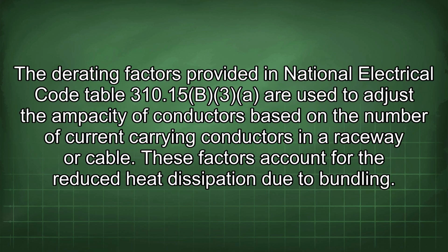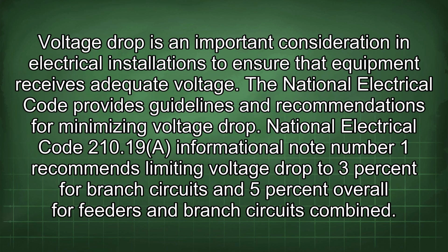The derating factors provided in National Electrical Code Table 310.15(B)(3) are used to adjust the ampacity of conductors based on the number of current-carrying conductors in a raceway or cable. These factors account for the reduced heat dissipation due to bundling. Voltage drop is an important consideration in electrical installations to ensure that equipment receives adequate voltage. The National Electrical Code provides guidelines and recommendations for minimizing voltage drop. National Electrical Code 210.19 Informational Note Number 1 recommends limiting voltage drop to 3% for branch circuits and 5% overall for feeders and branch circuits combined.